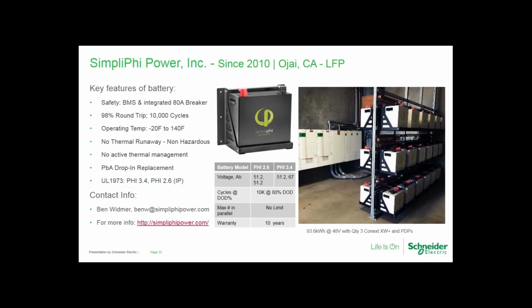And then Simpliphi Power, finally, is another drop-in replacement for lead acid battery. They don't have any comms, but the BMS is built into the battery, and there is a breaker also situated on the same battery. So again, as long as you're setting up the battery according to their recommendations for charge voltage and max charge rate, then it's considered compatible, and there's really no additional steps to take in that regard.